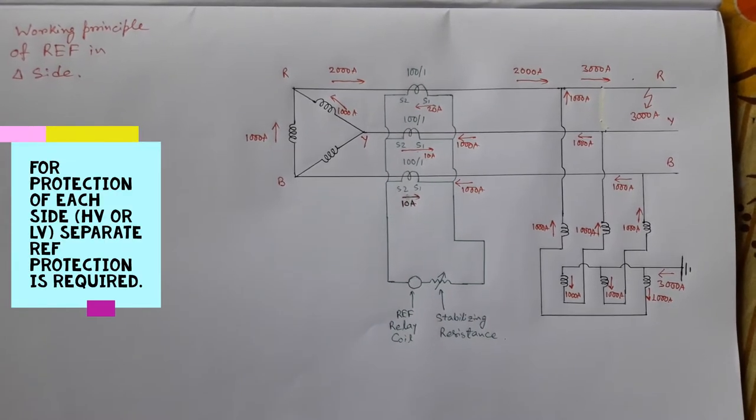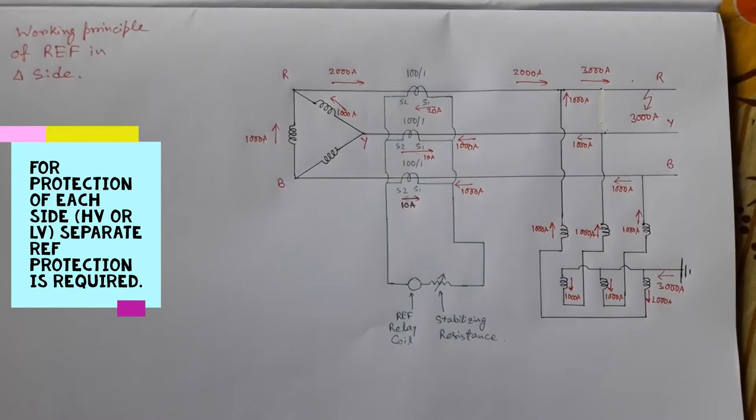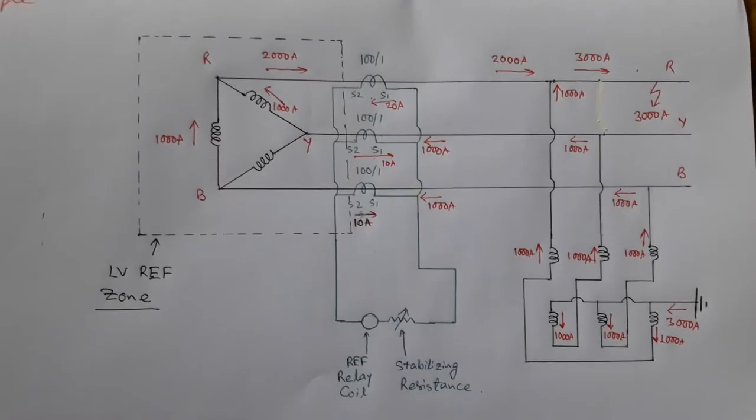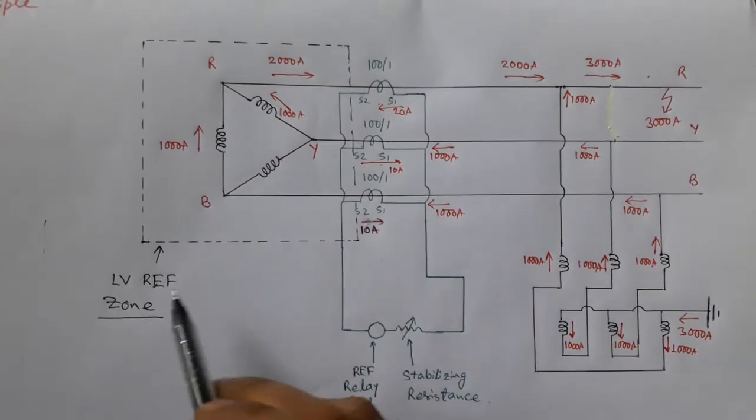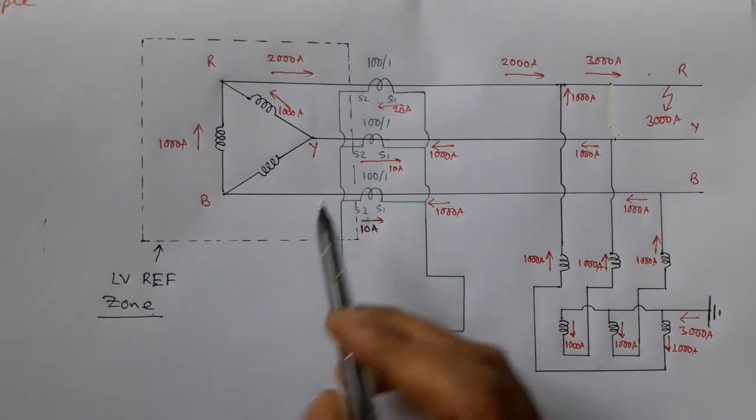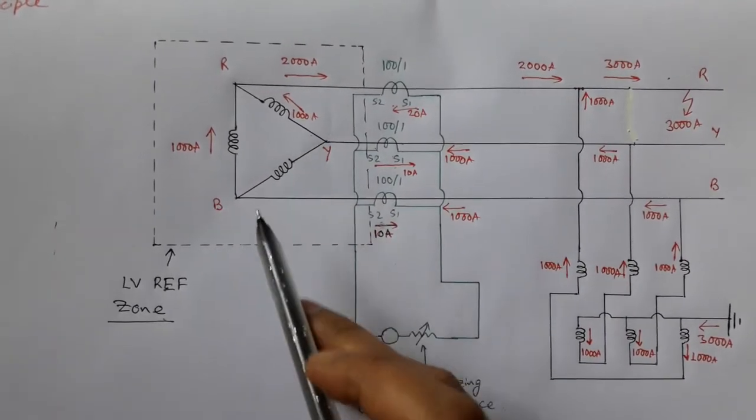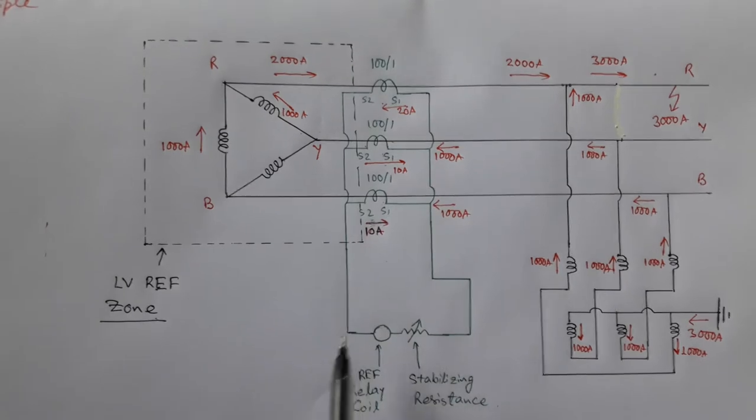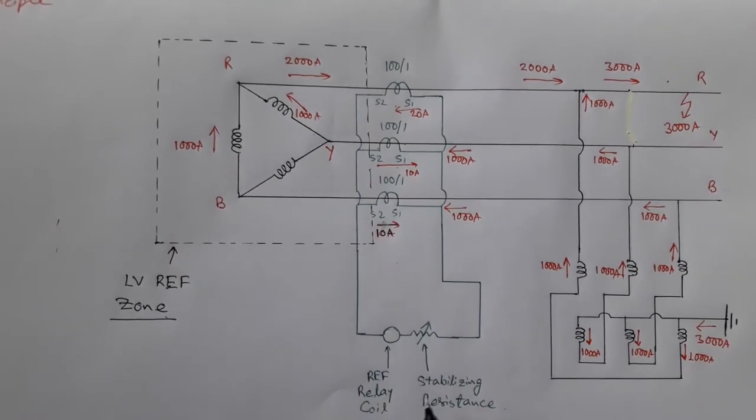In this video we will discuss how a REF relay can protect the delta side of a power transformer. In this diagram, this dotted line represents the restricted earth fault zone. That means if any fault appears in this restricted zone, then that fault will be cleared instantaneously by operation of the restricted earth fault relay.